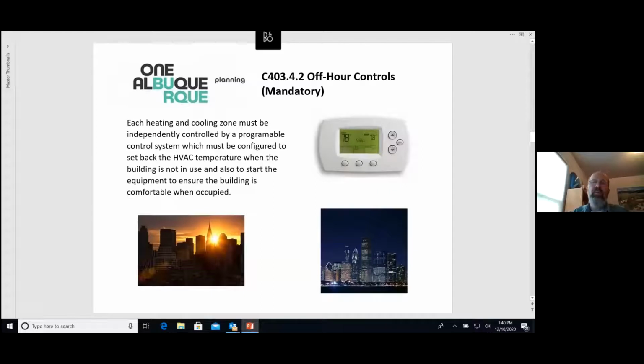So, off-hour controls. Heating and cooling zones are independently controlled by some sort of programmable control system. Those systems will be set back when the building's not in use and start the equipment before it's occupied so it's comfortable. So that's just another functionality. At the end of the day, everyone goes home, it automatically rolls it back, cools the building a little so you're not heating it when it's not needed, and warms it up so when people get there, it's comfortable.